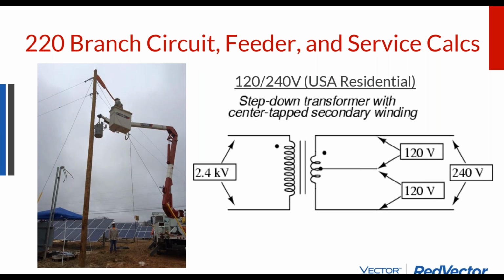And so we step up the voltage to transport electricity over very long distances, because by and large, voltage is cheap and amperage is expensive. The thickness of your metal wire is more related to amperage. The cable jacket is more related to voltage capacity. The power lines might not even have a cable jacket. They just space them out so that the air is the insulation.